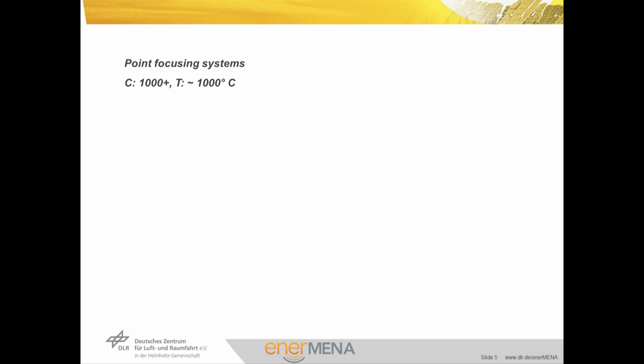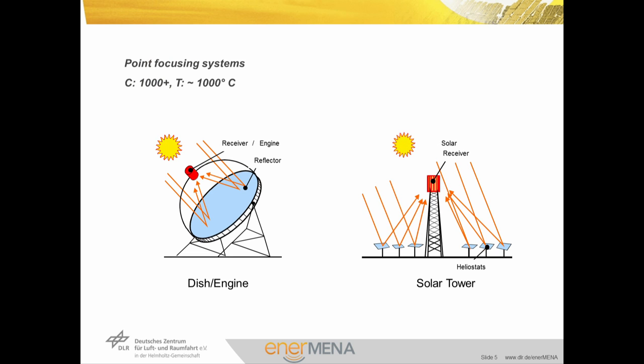Here we see the point focusing systems, for example the dish engine or the solar tower. Both systems concentrate the sun energy in one point in the receiver. Those point concentrating systems reach concentration factors of 1000, meaning 1000 suns come together and produce a temperature of 1000 degrees. But for our steam production we only need 500 degrees, so those systems should perhaps use other process technologies like the Stirling motor or gas turbine.